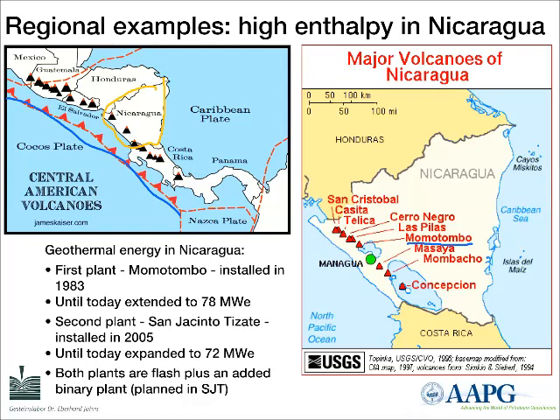The first geothermal plant installed in Nicaragua was the Momotombo plant in 1983, which has produced 78 megawatts until now. In the neighborhood, a second power plant — the San Jacinto Tizate — was started in 2005 and today has some 72 megawatts installed. This is not only a flash plant but also includes a binary plant — so we have a flash process producing steam to run a turbine, and for remaining heat we can run an ORC or Kalina-type binary plant. With enough heat remaining, we could even make direct use for fish farming or greenhouses.